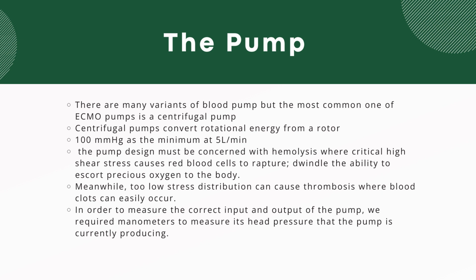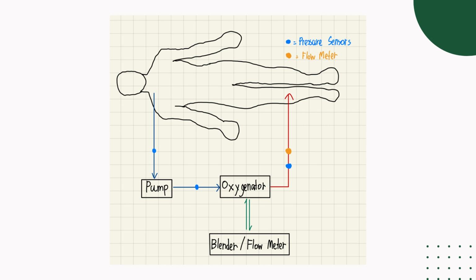stroke. So in order to measure the correct input and output of the pump, we are required to set a manometer or pressure sensors to measure the head pressure that the pump is currently producing. Oh, I forgot to mention, the head pressure here is the pressure that drives the blood across the circuits. The pressure sensor or manometer will be placed on the inlet of the pump or the venous drainage cannula. This one will show a negative pressure in the display, so it's basically the amount of work that the pump needs to do in order to drain the blood from the patients.